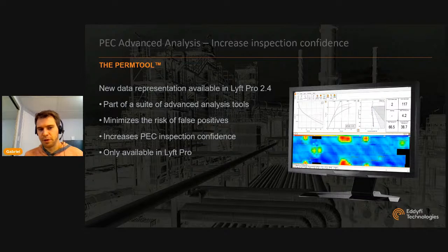The tau scan and the PERM tool are not meant to be used individually. They're part of a suite of advanced analysis tools, amongst others, including the CWT. So we're really building a platform in Lyft Pro where you have all these advanced analysis tools and you can increase your understanding of what's going on in the PEC data and get better inspection confidence. And this new tool, the PERM tool, is only available in Lyft Pro. So the tau scan, we've got the calibration tau scan on the LIFT Go unit so that if you're in the field, you have the wrong weather jacket material, you see the calibration delay, you see the calibration tau scan, and you can see those issues in the field, change the component definition, recalibrate accordingly, and then you've got the signal tau scan in Lyft Pro. But the PERM tool is only available in Lyft Pro. And we're going to load this layout with the PERM tool as soon as you open data in Lyft Pro 2.4, R16, and later.